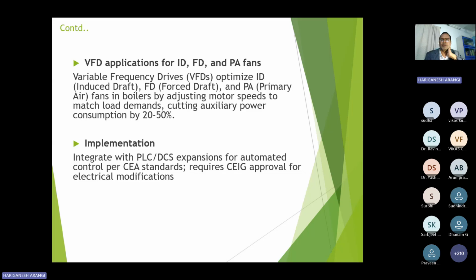The next efficiency measure is VFD applications in the ID, FD fans, cooling towers, cooling water pumps, and BFPs. Initially we have no need for fans to rotate at their rated design speed, because initially it requires only less speed as the initial load will be very low. At that time, by operating the motor at full speed, you are unnecessarily wasting energy. So by installing variable frequency drives, we will optimize the power also.